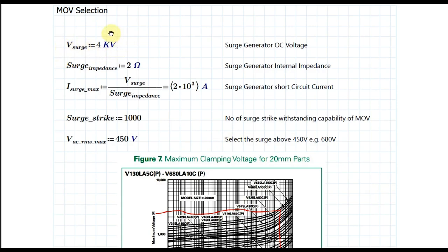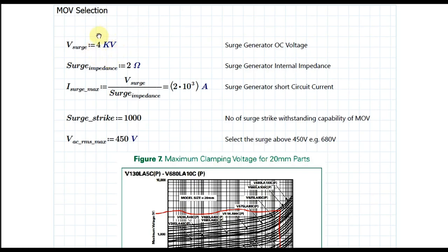If you know the IEC standard IEC 61000-4-5, it states that for Class 4, your surge voltage is ±4 kV. This is basically the surge generator open-circuit voltage, which you can also call the Thevenin voltage — so this is a 4 kV surge generator Thevenin voltage.